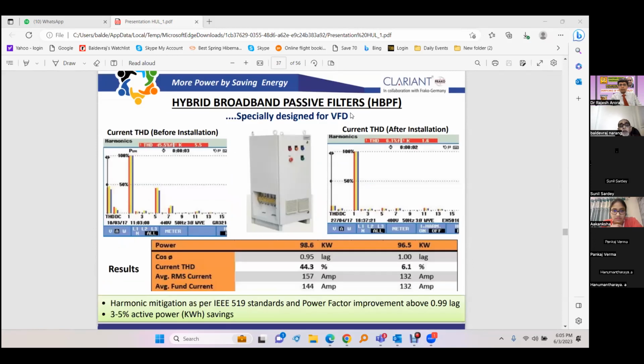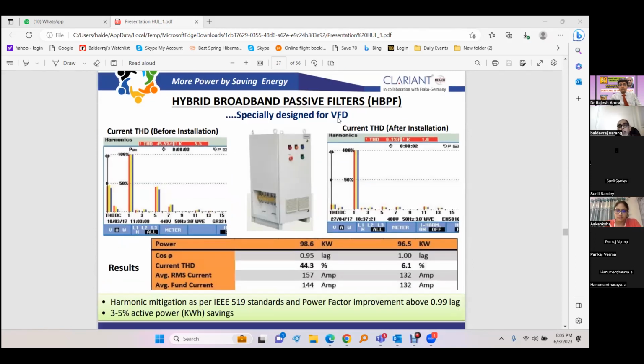This is another passive filter, which is used directly in series with what we call a VFD. A VFD initially has harmonics from 40 to 60%. If it has a series reactor inside, it will be say 40%. If it doesn't have a reactor built in, it will be around 60%. So we are using this hybrid broadband filter. It has a series filter and a shunt filter, both passive, and this takes care of both lower order as well as higher order harmonics. We are able to get down to around 5-6%. In fact, we are giving it to some OEM companies, and they supply it along with the VFD.